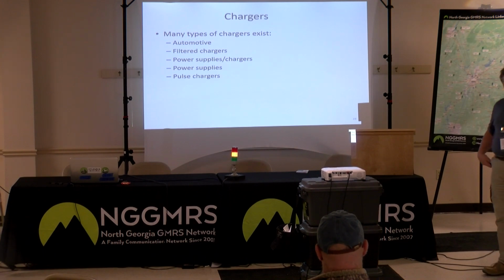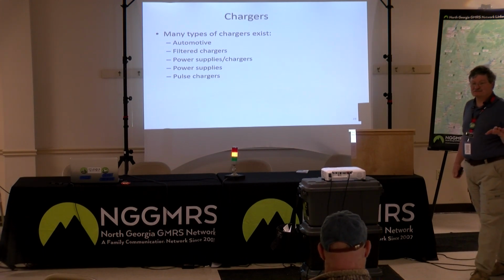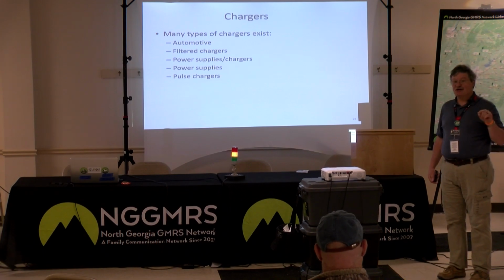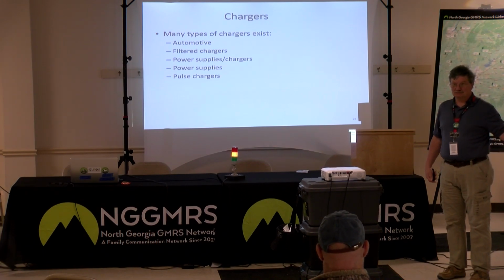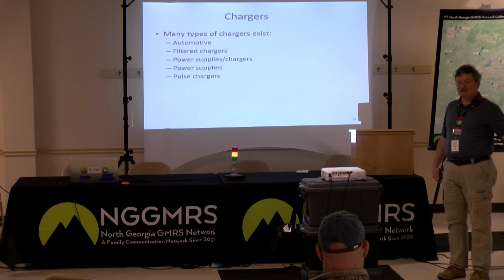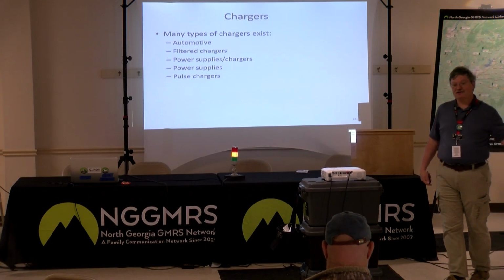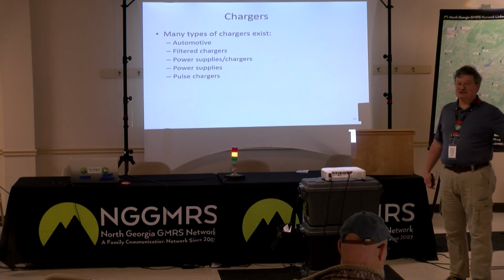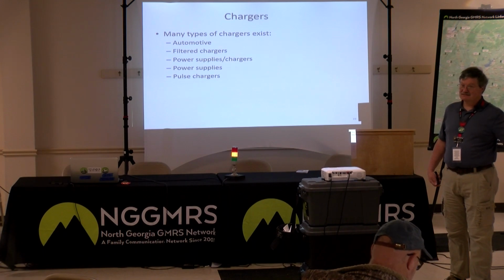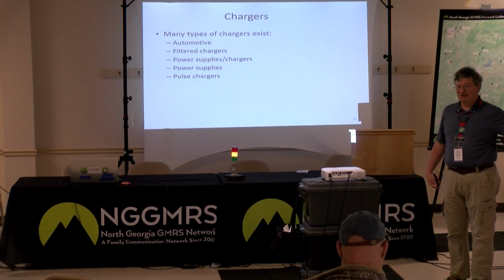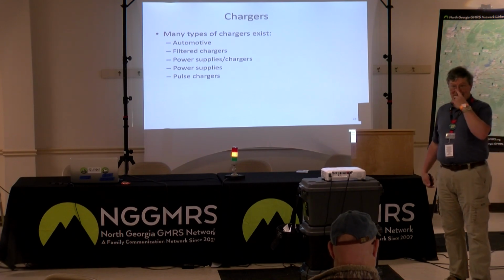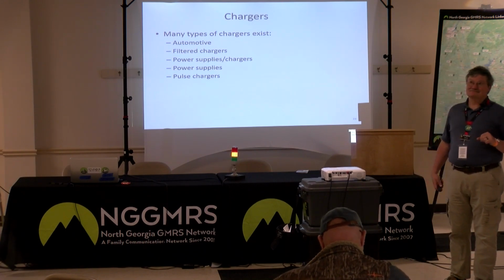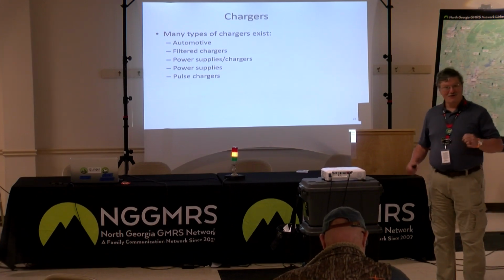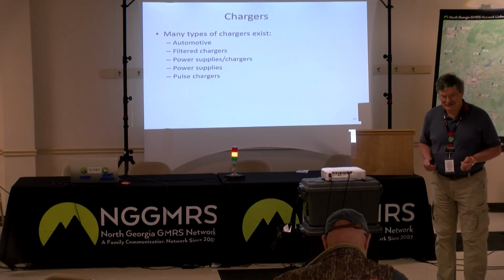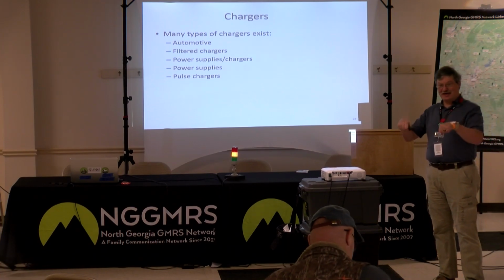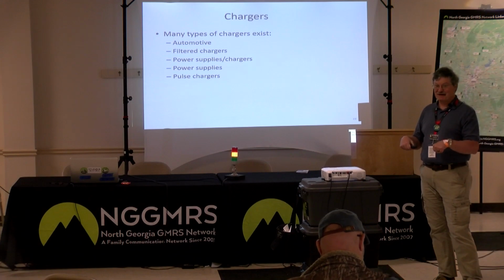Be careful using a power supply to charge batteries. Some power supplies do not like a substantial energy storage device on the output - could be a monster capacitor, could be a battery - but under the loss of AC, some of those circuits expect that energy to dissipate and go away. If it stays there too long because I've got a battery or a big capacitor bank out there, it makes things die. My former employer knows about that - we have power supplies where we put diodes in, or we hook up a diode external to the power supply to protect it should there be a power failure.